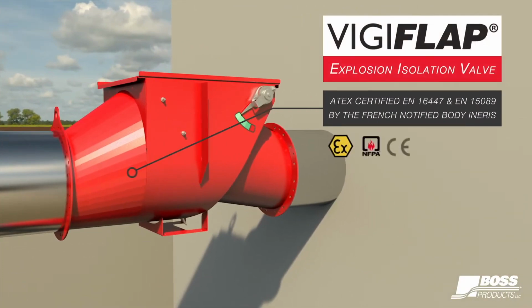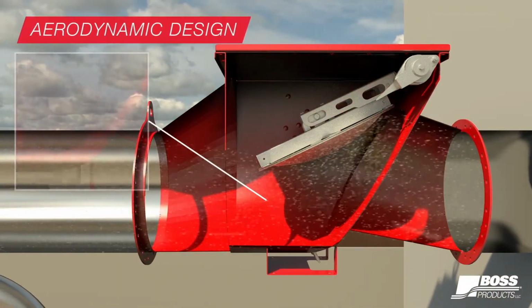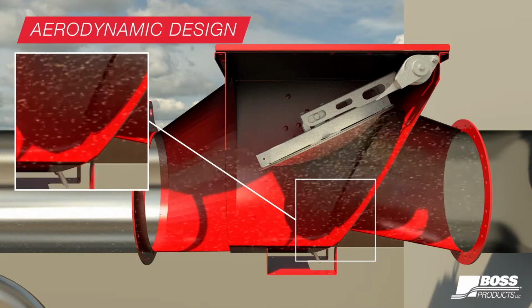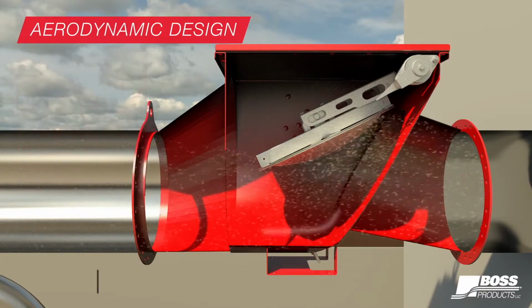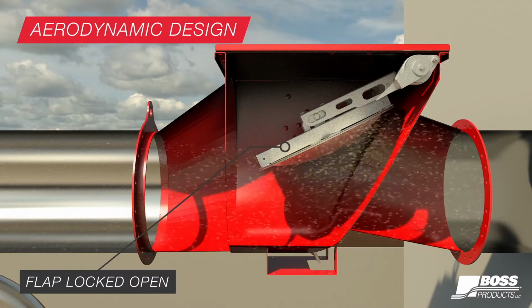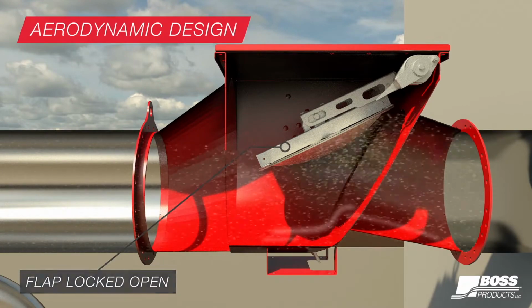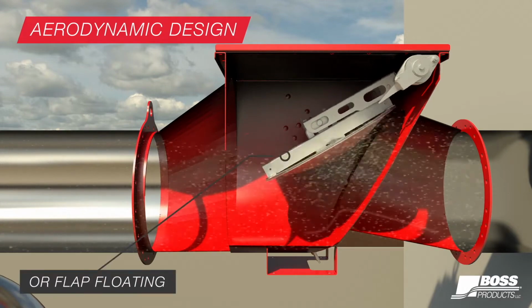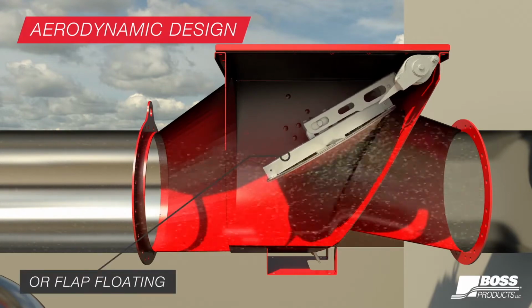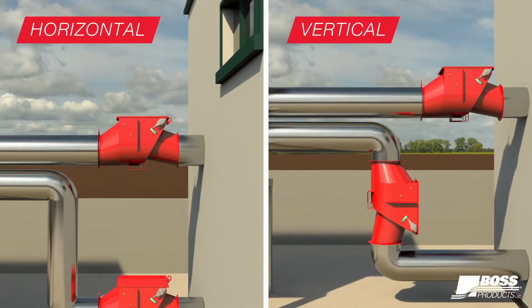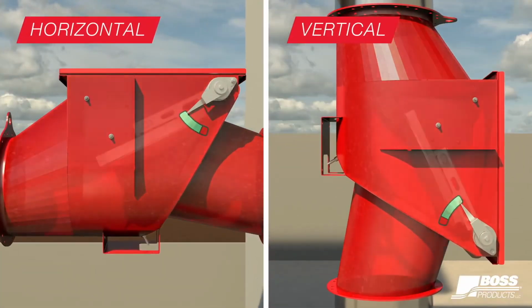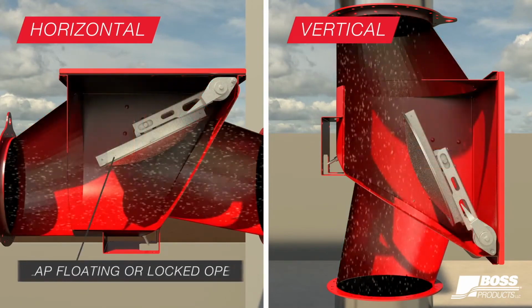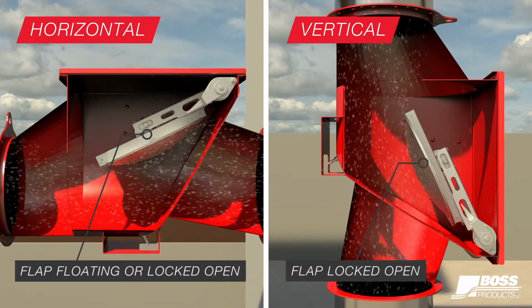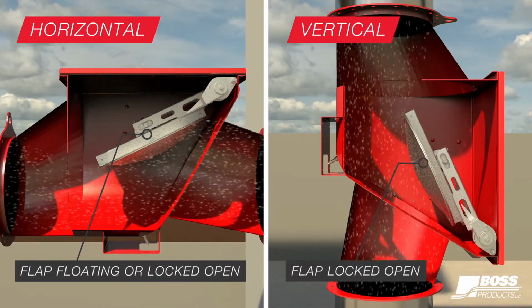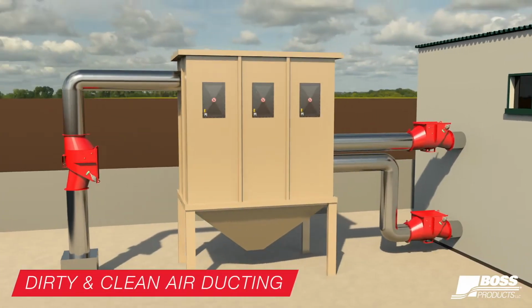And again, it shows you the pressure closes that flap, and then the fireball comes always after the pressure wave. With the round design, you have minimum pressure drop, so you're not losing your airflow in your process. And there's different positions of the flap. It showed a floating position where basically the airflow is keeping that flap open. And then you can also do it in a flap locked open position, where it's locked in the open position as well. And you can install it vertically as well.